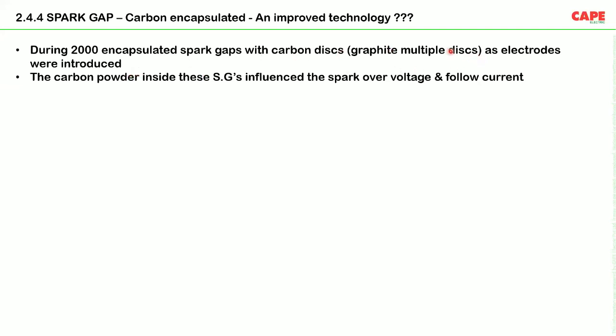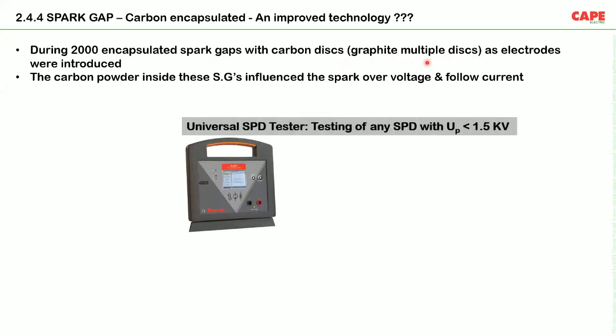So these devices actually have a funny principle, or a funny parameter. This graphite electrode has graphite powder inside. So if you shake the device with your hand, probably the carbon powder inside the spark gap accumulates in one portion of the spark gap. And now if you test the spark gap with an SPD tester, what happens is the parameter, the voltage protection level, keeps on changing.